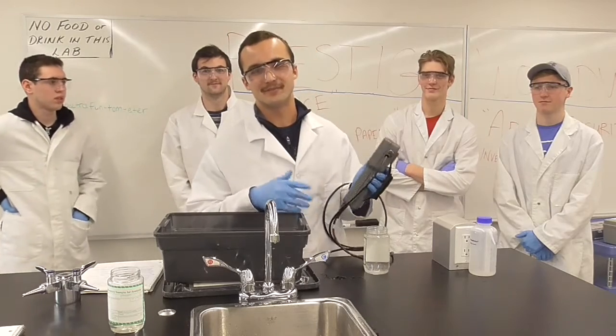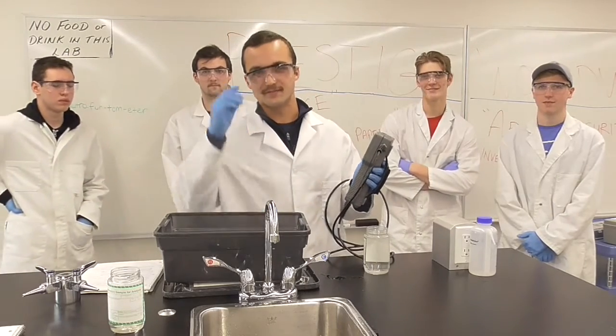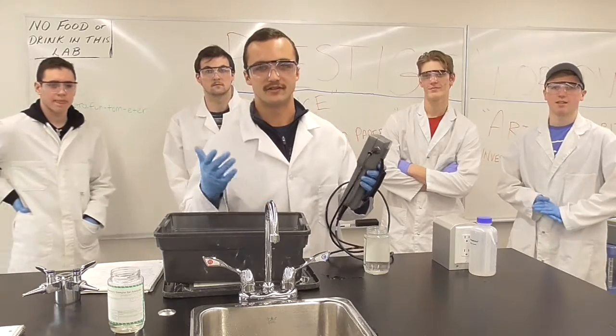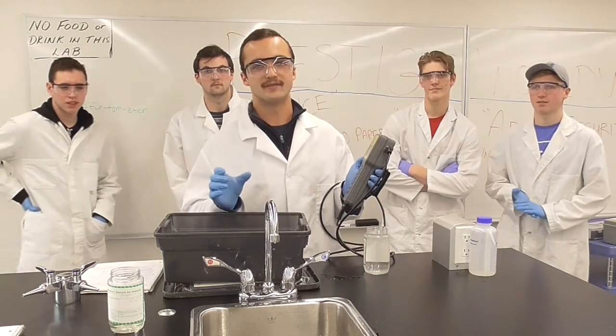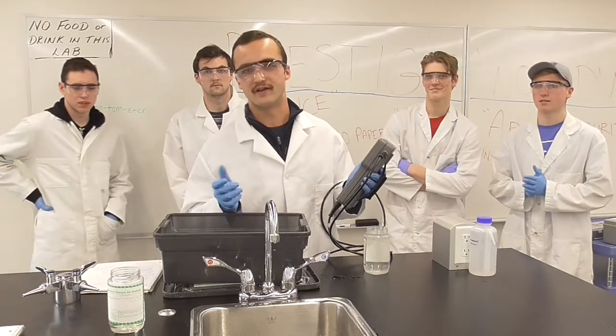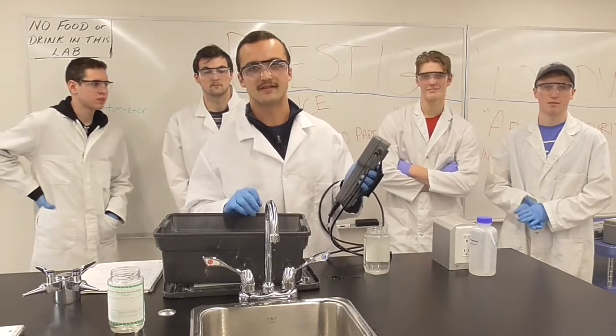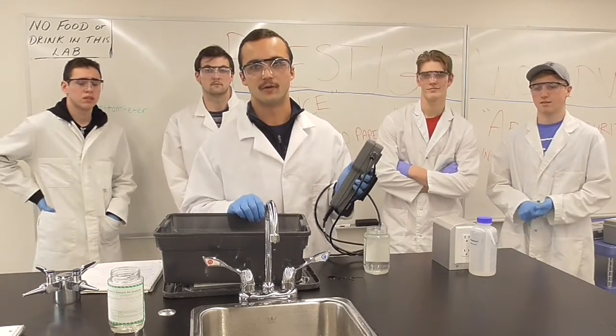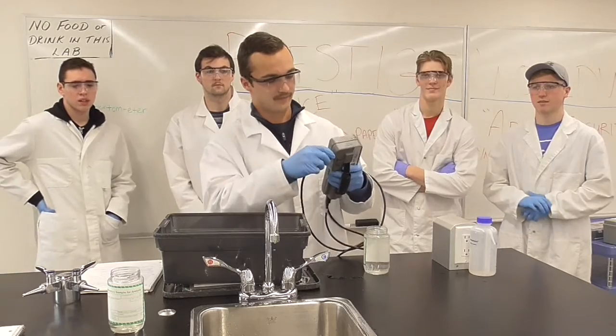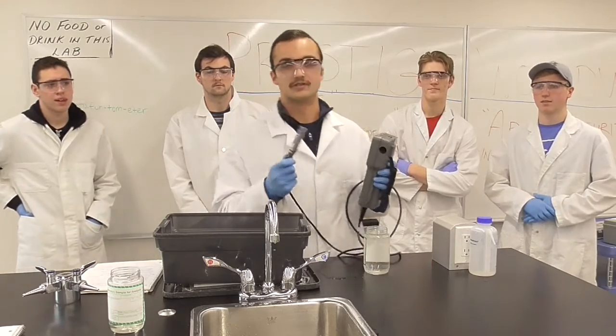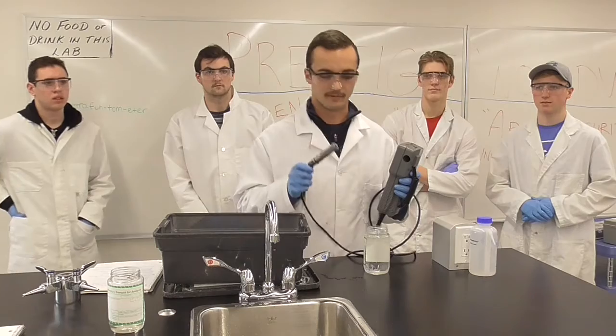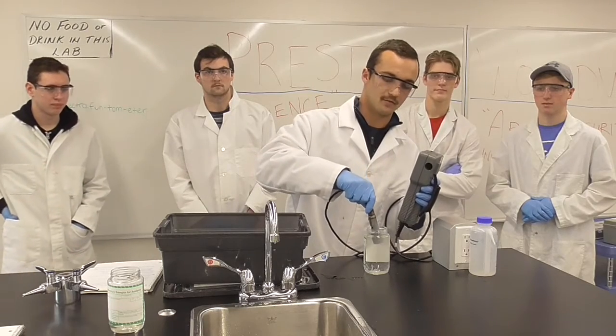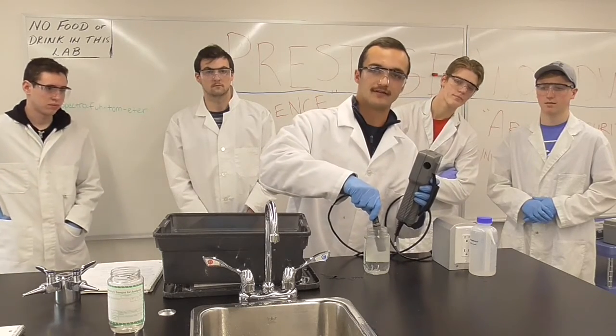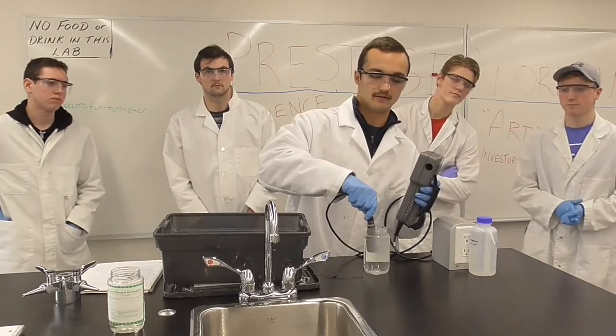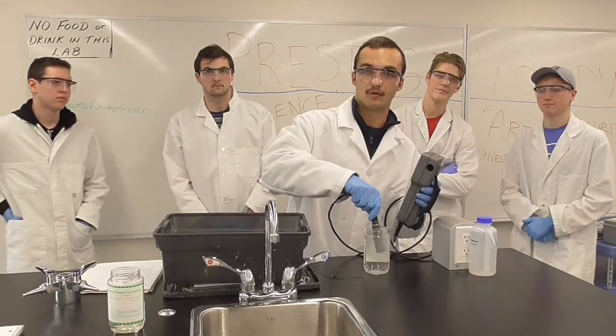We know that it's measuring specific conductance. Specific conductance is measuring the conductivity, but at a specific temperature, which is 25 degrees Celsius. So it gives us an accurate reading no matter what temperature the water is at. To actually measure the conductivity of the water, we're going to place our probe fully submerged in the water, and then we will actively stir or bob the probe.